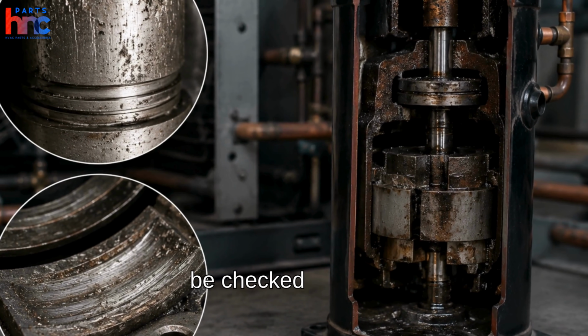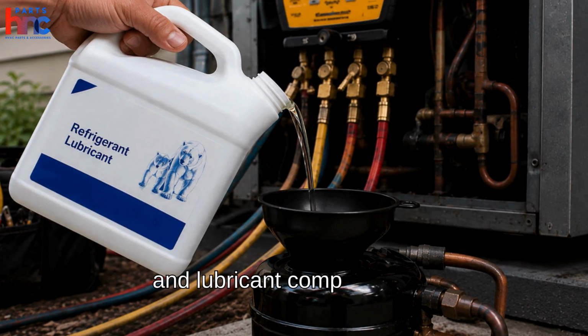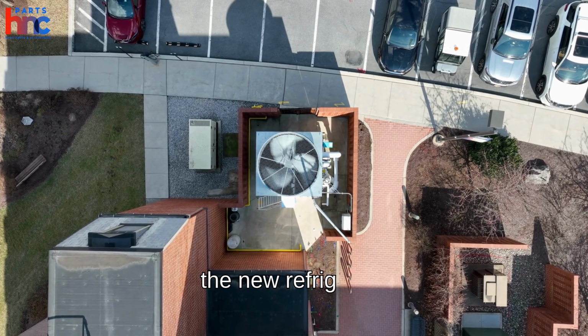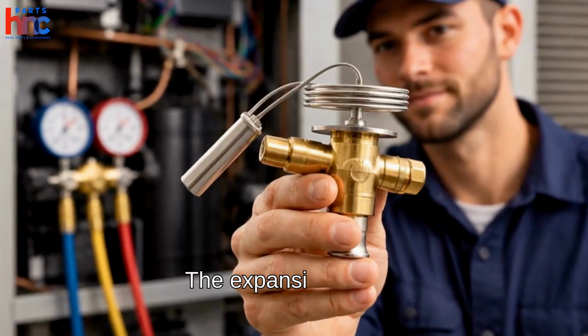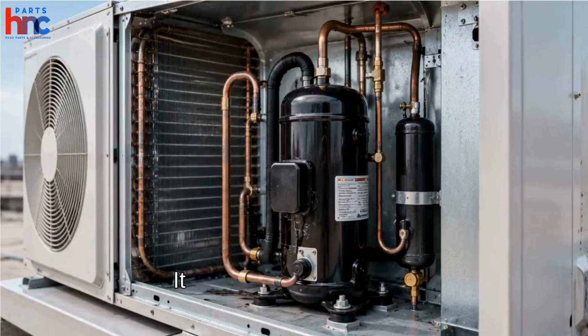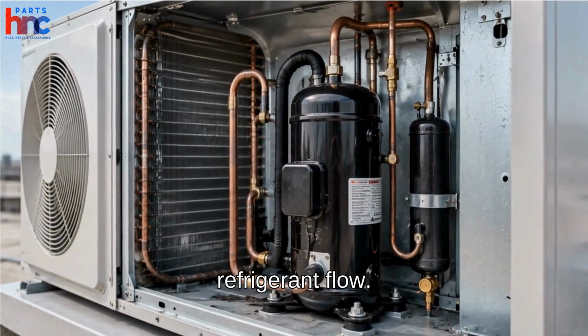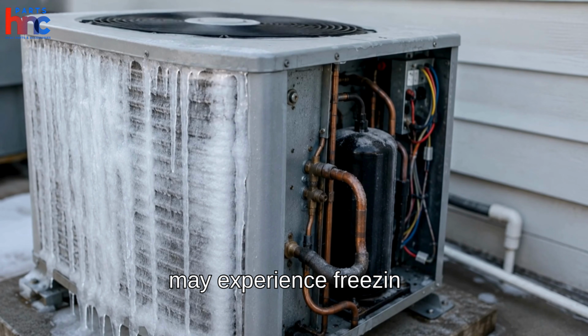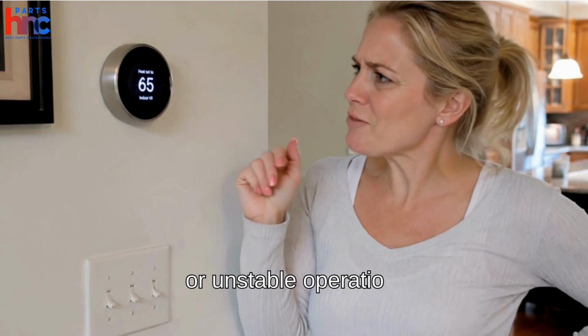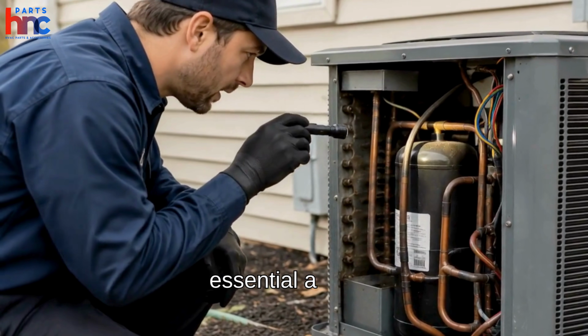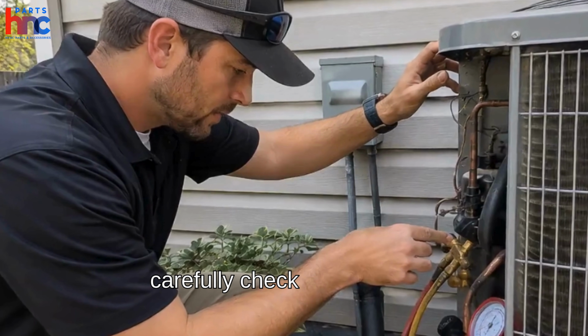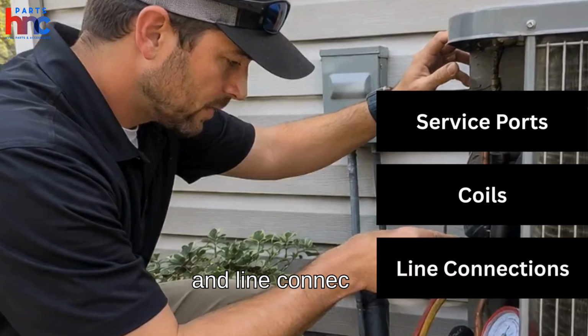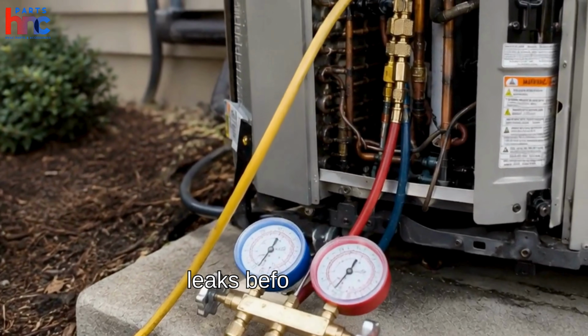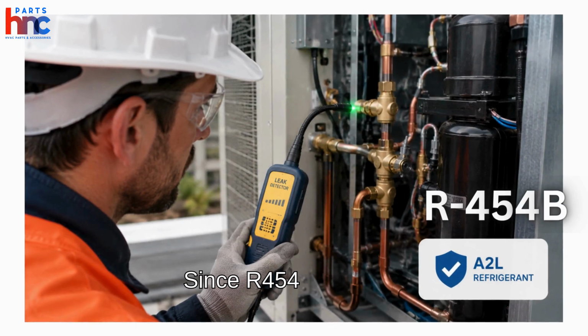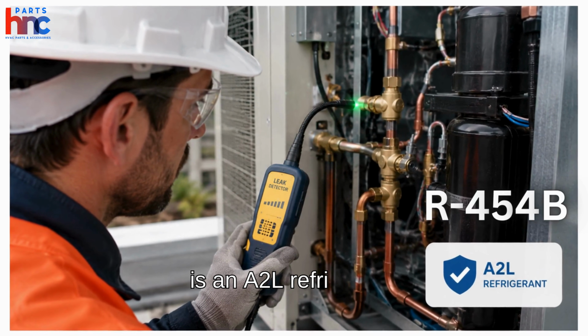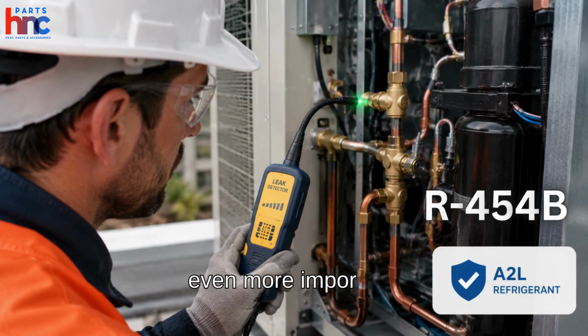The compressor must be checked for wear, overheating, and lubricant compatibility to ensure it can handle the new refrigerant without failure. The expansion device is also important. It must properly regulate refrigerant flow. Otherwise, the system may experience freezing, poor cooling, or unstable operation. Leak inspection is essential as well. Technicians carefully check service ports, coils, and line connections to ensure there are no refrigerant leaks before charging the system. Since R-454B is an A2L refrigerant, leak checks become even more important.